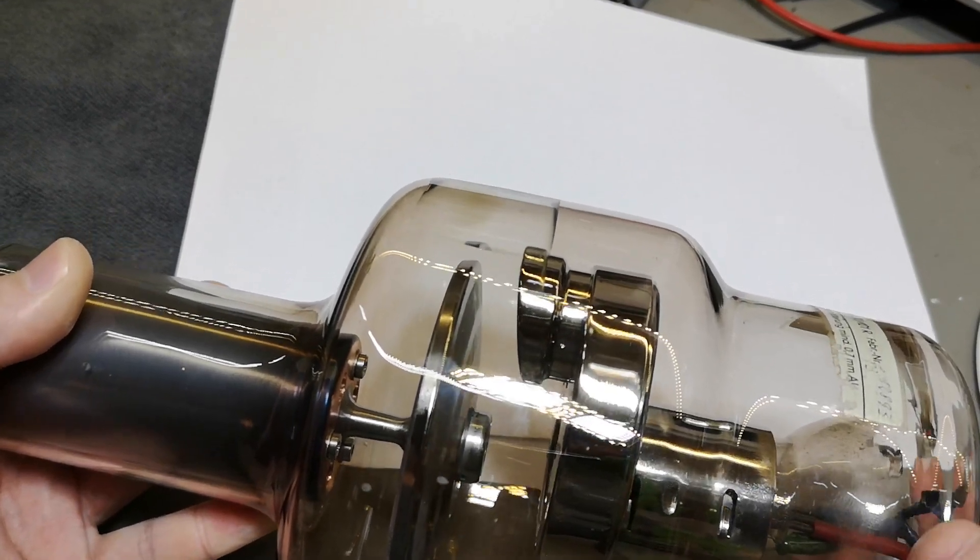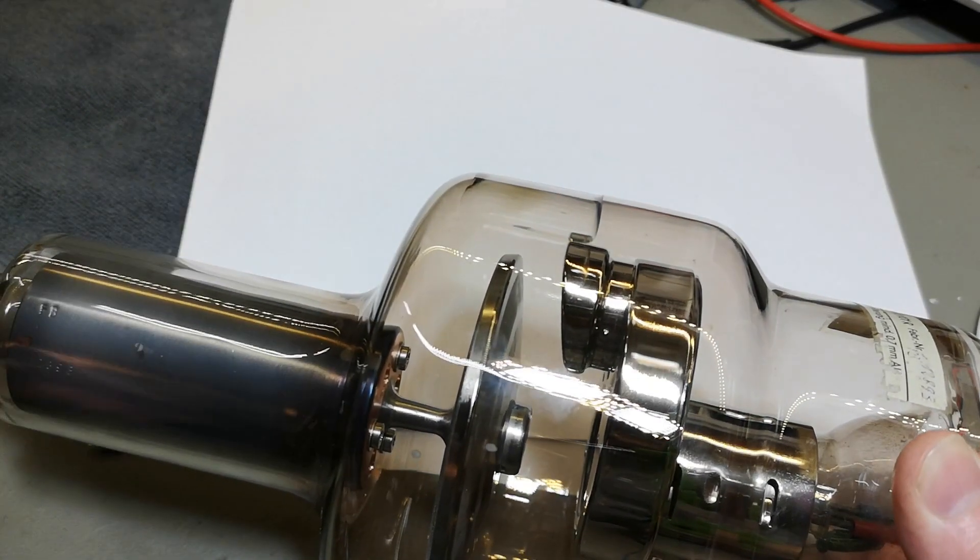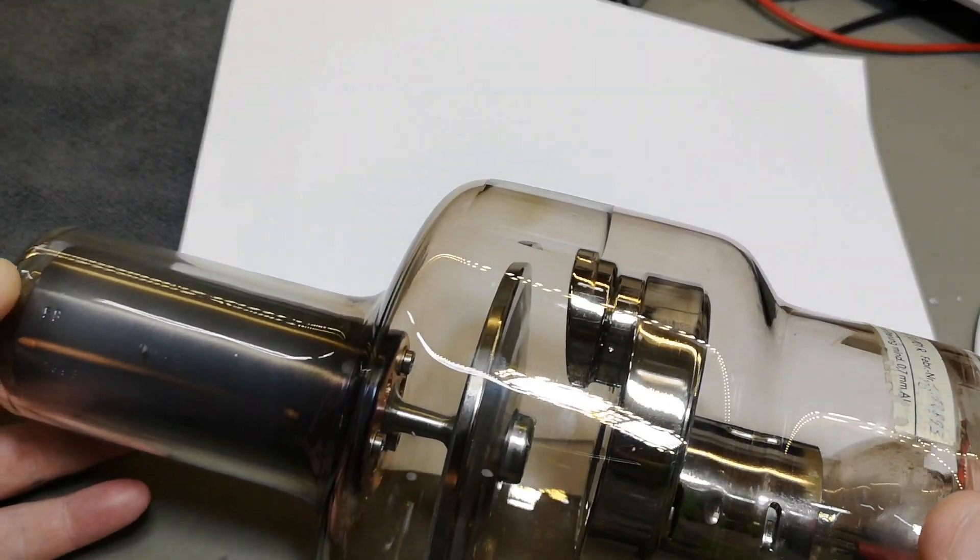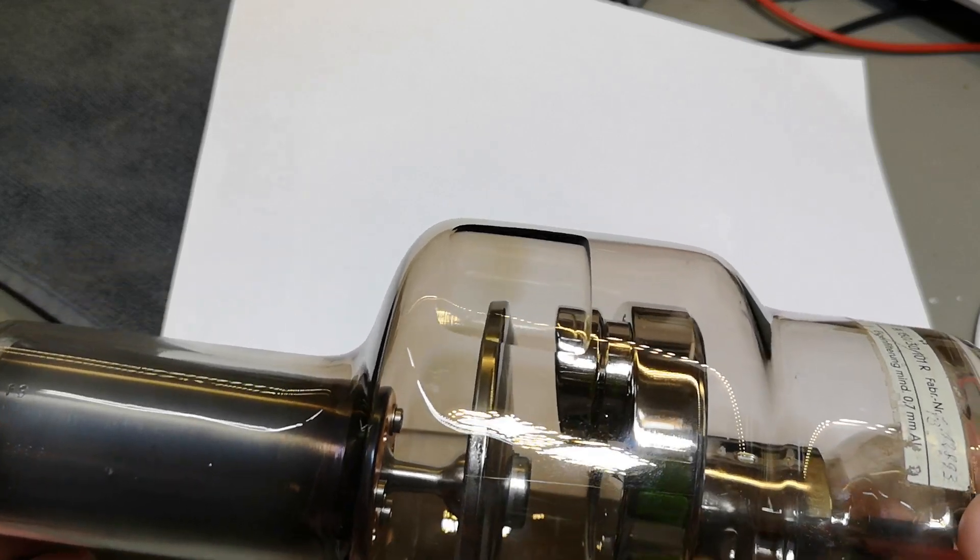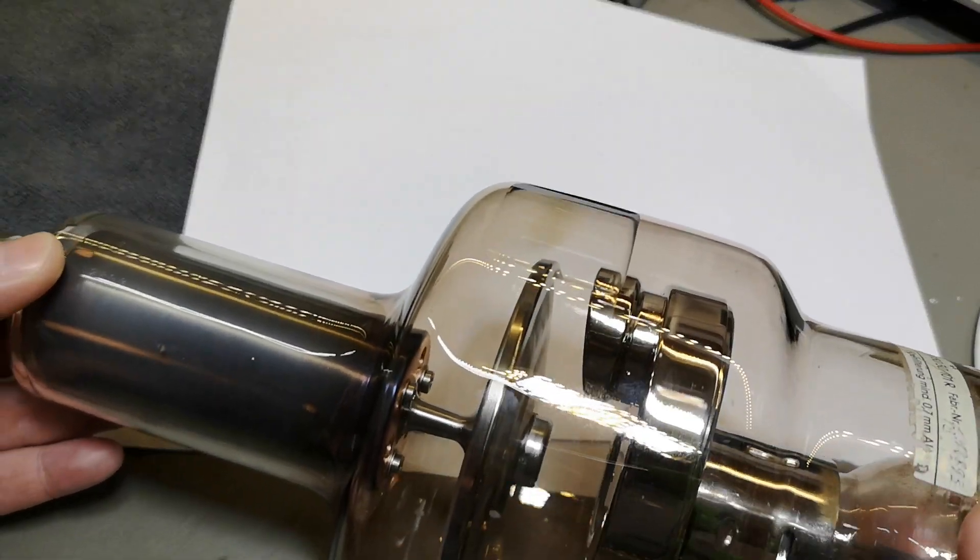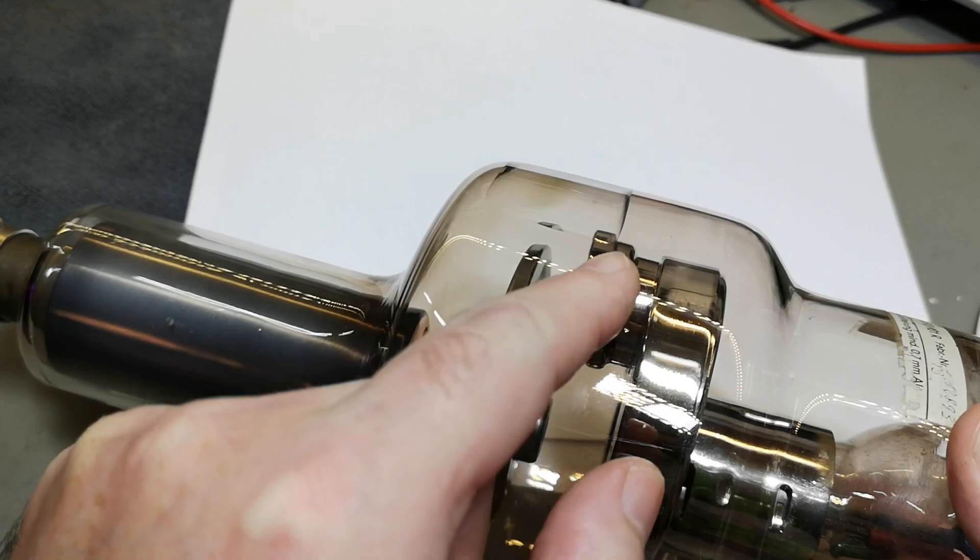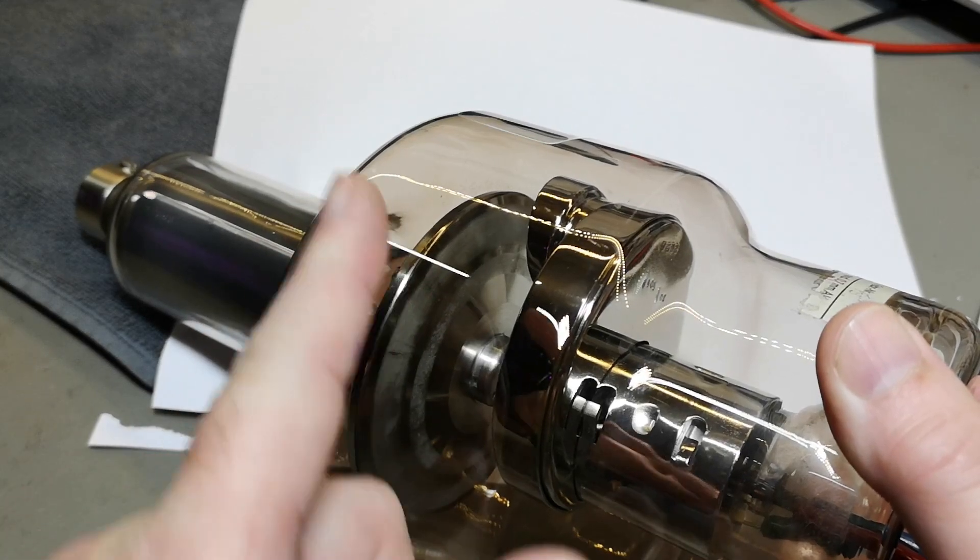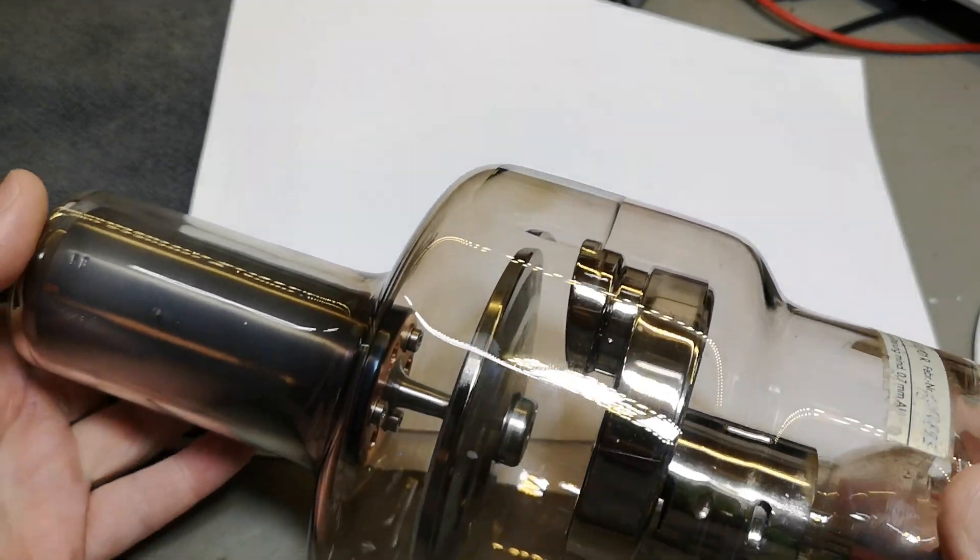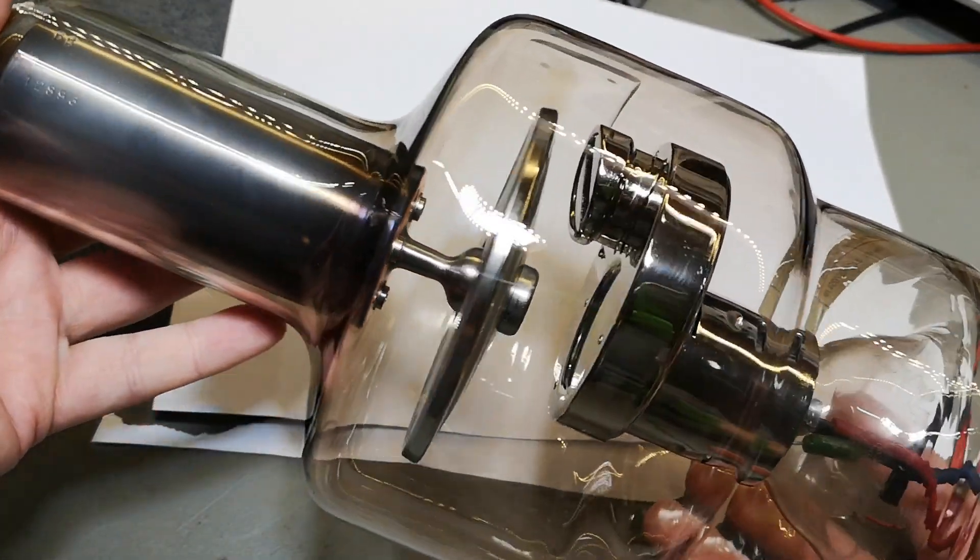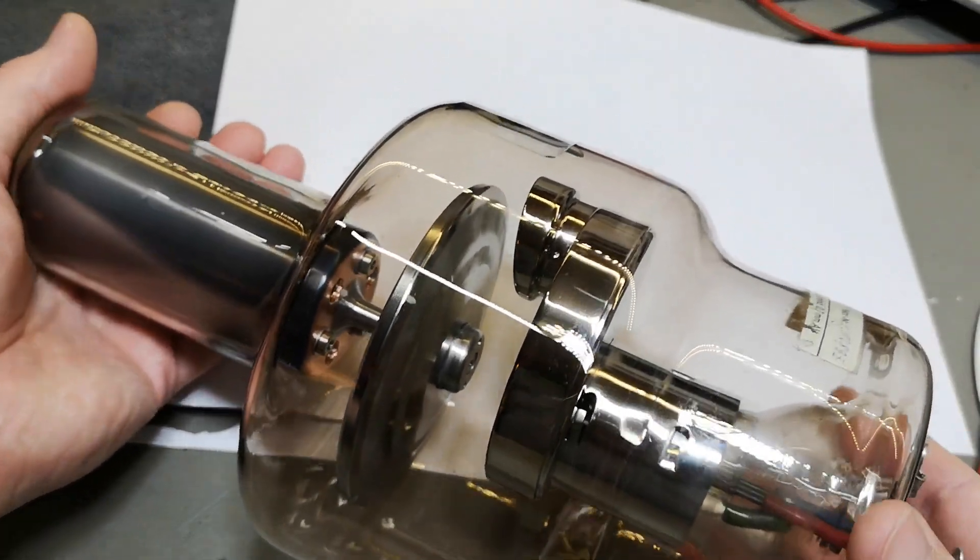Let me show you this - I want you to look at this area of the glass. It's actually a little bit darker where all the X-ray is coming out, so it's actually discolored or added a little bit of material. Something happened to the glass. It could also be filament material and cathode material hammering down here on the anode and some of it's actually ejected to the glass.